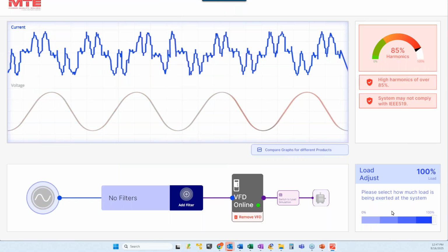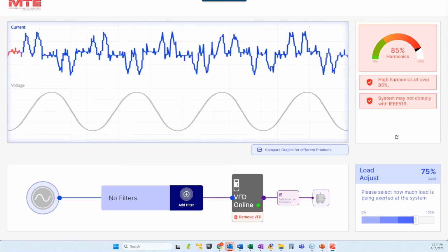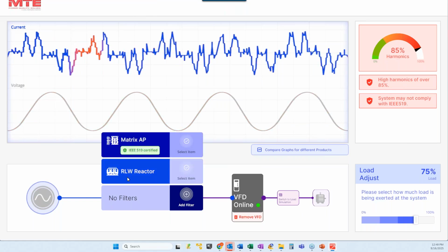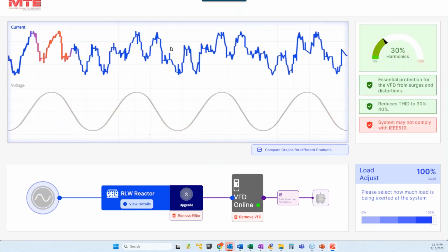I can also adjust how much load, but basically, it doesn't affect it a lot. High harmonics, 85%, doesn't comply with IEEE. Now MTE makes 2 different filters. I can put an RLW, and that'll clean it up some. I got the harmonics down from 85% to 30 to 40%, but I'm still probably not complying with IEEE.